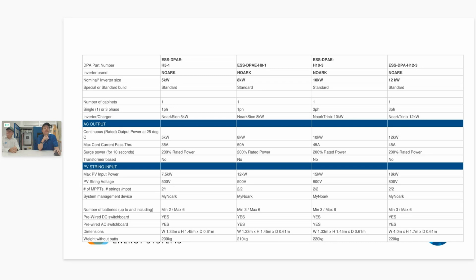So the question: does the Discover battery BMS terminate at 55.2? The way it works is the battery is broadcasting its maximum charge voltage to the inverter, and that's a dynamic value. It does that for a couple of reasons, but a lot of it's to do with the balancing of the cells. So if it wants to balance the cells, it'll broadcast a lower target voltage for the inverter to take the batteries up to, and once it's finished balancing, it'll broadcast a higher voltage, which is the end of the absorption phase.